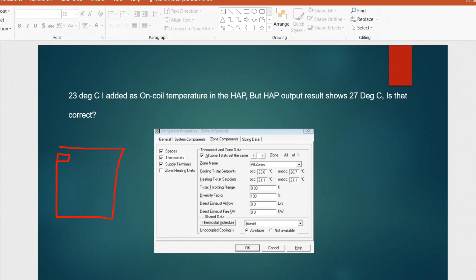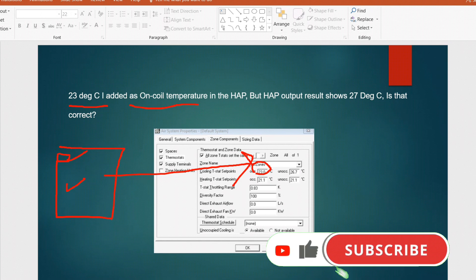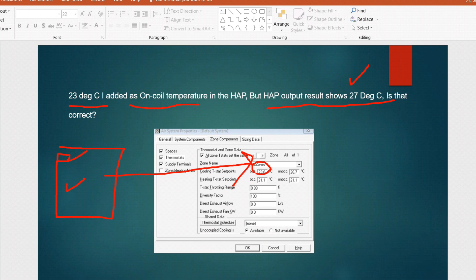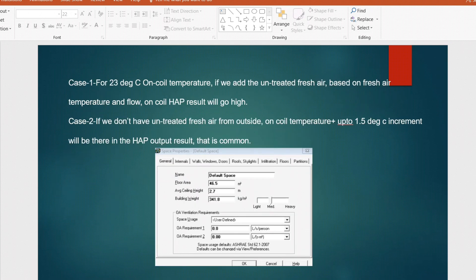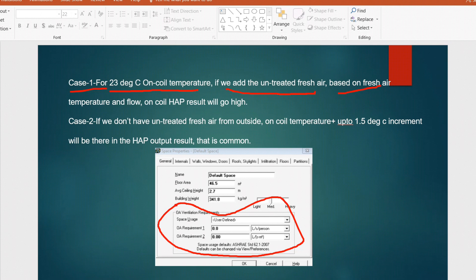The next question related to HAP cooling load calculation: if I have a room where I want to maintain 23°C as the comfort condition and I enter 23°C in the HAP thermostat, but the HAP output shows 27°C — is that correct? There are two important cases. Case 1: if untreated fresh air is added, based on the fresh air temperature and flow the on-coil HAP result will go higher. Case 2: if there is no untreated fresh air from outside, the HAP output will be the thermostat value of 23°C plus a maximum increment of 1.5°C — so maximum 24.5°C in the HAP output.